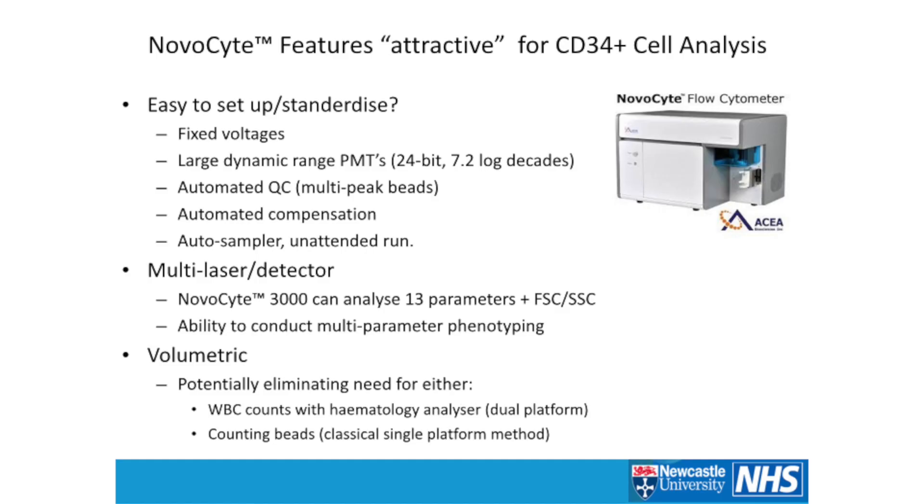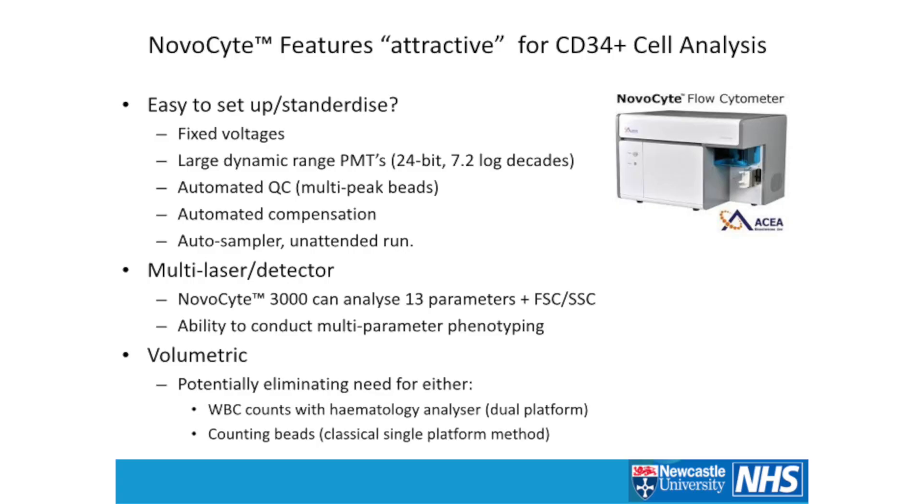This is really why I thought it would be interesting to evaluate the NovoCyte. What makes it attractive for enumeration of CD34-positive cells? It's quite easy to set up with built-in standardization: fixed-voltage wide-range PMTs up to 24-bit with a 7.2 log decade, so no need to go in and set up PMTs. It has automated QC using six-peak multilevel beads — familiar and giving an idea of sensitivity and linearity. It has an automated compensation wizard, which works quite well. And it has an auto-sampler for unattended runs. As a multi-laser, multi-detector system, the 3000 model can go up to 13 parameters with forward and side scatter.